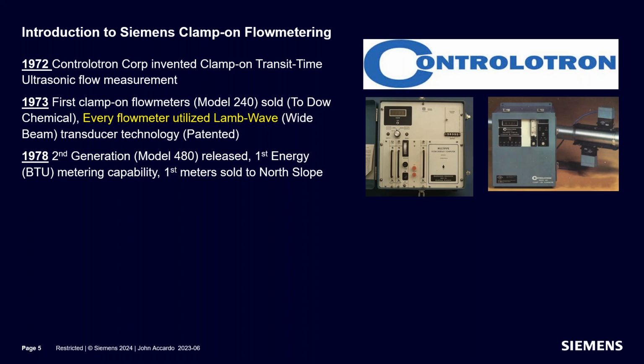Every single one of these meters was also a custom product. If you're familiar with the clamp-on meters, you know that we require an application data sheet, which gives us a look at what your application is. What are you flowing? What is your pipe size? What is your liquid, and so on. Back then, we needed to know everything. We needed to know what your pipe was, what your fluid was, what flow units you wanted the meter to read in, and so on and so on.